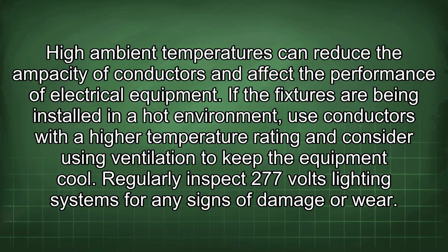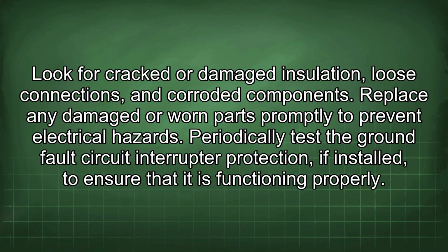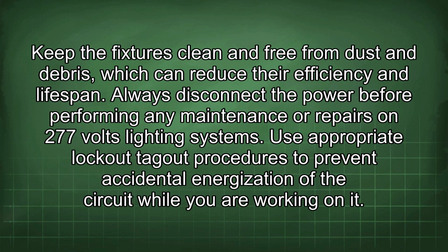Regularly inspect 277 volts lighting systems for any signs of damage or wear. Look for cracked or damaged insulation, loose connections, and corroded components. Replace any damaged or worn parts promptly to prevent electrical hazards. Periodically test the ground fault circuit interrupter protection if installed to ensure that it is functioning properly. Keep the fixtures clean and free from dust and debris, which can reduce their efficiency and lifespan.